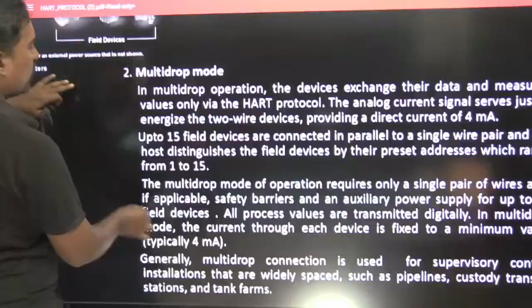Now, in multi drop mode, what is the point here? I want to tell you. Multi drop means what? See here. Are you able to see this? Previously, what I explained was the point to point connection. I think all of you are able to see this picture clearly. Multi drop means the different field devices are connected to the two masters, primary master and secondary master, on the same 4 to 20 milliamperes line. Do you understand? We don't have any separate lines; on the same 4 to 20 milliamperes line, this sensor, this sensor, this sensor are accessible, and not only sensors, actuators also. So, that is multi-drop mode.